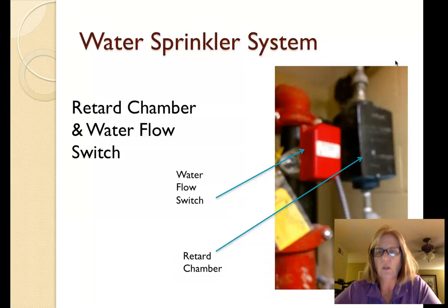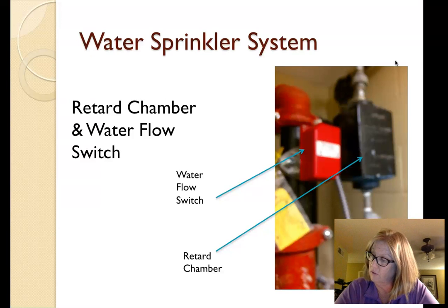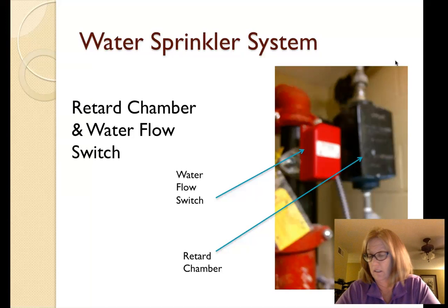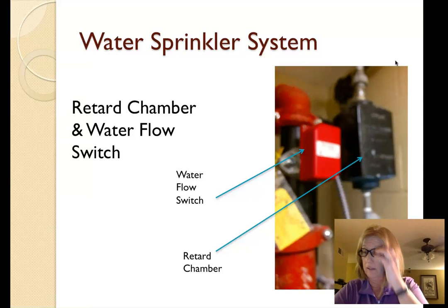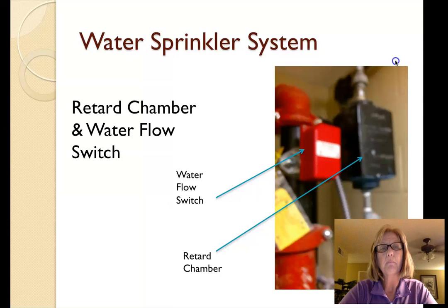He said that this was an old school way of notification, even though it still works. A water flow device, which you can see here, a water flow switch, works better. It's basically a vane inside of it that notifies the alarm company of system activation. So when the vane inside the flow switch is moved up by water activation, the micro switch sends a message to the alarm panel and says the alarm has been activated.